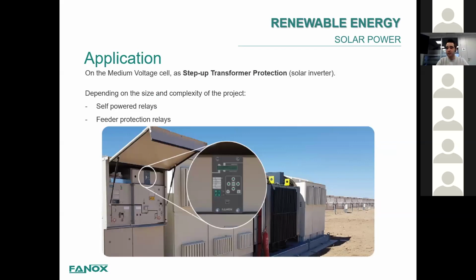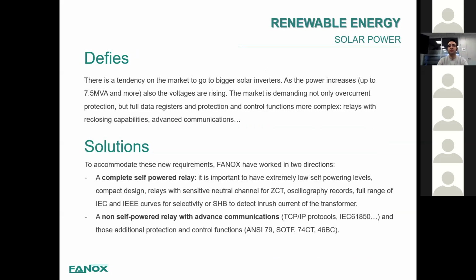Now we're going to move to solar power, to the photovoltaic market. Our relays are typically installed on the medium voltage cell as the protection for the stepped-up transformer, the solar inverter. Depending on the size and the complexity of the project, we have two different approaches. The first one is self-powered relay, for all the reasons we have spoken about before and some that we are going to see now. But as the size increases and the complexity of the project becomes bigger and bigger, they require a protection relay with the protection functions and the capabilities of a traditional feeder protection. And we are working on those two different ways.